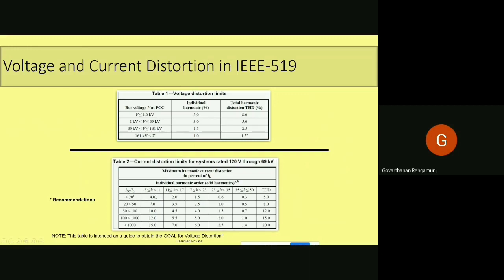Here, as I already said in the preface, there are different THD or TDD limits in the last column with respect to different short circuit ratio. This short circuit ratio is nothing but ISC by IL. ISC is the short circuit current at the grid, and IL is the rated load of the equipment, or the demand current. So this gives the short circuit ratio. Each short circuit ratio will give different limits for TDD and different orders of harmonics.